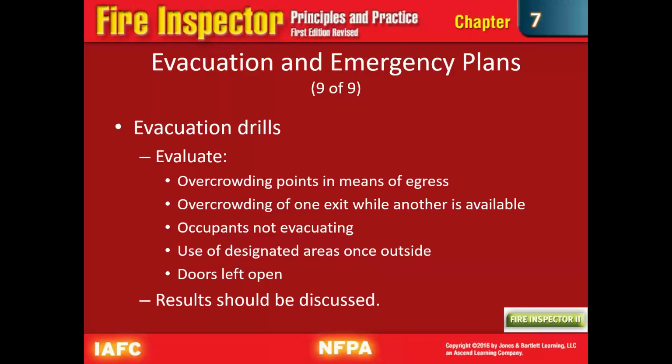Another thing you may determine: in one of the drills that I helped the organization with redrawing, their drill consisted of them walking out of one building and walking through another building to access their refuge area or their safe area. Well, what if the incident was in that building? What are they going to do? They also always planned to go to the back of the facility. Well, what if the emergency's at the back and there's ample space in the front? So again, fluidity of plans.